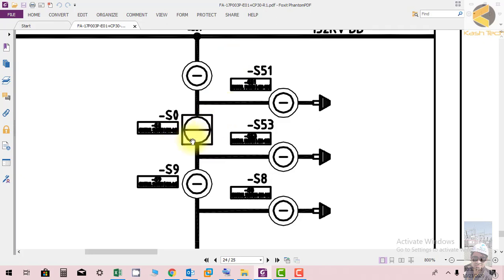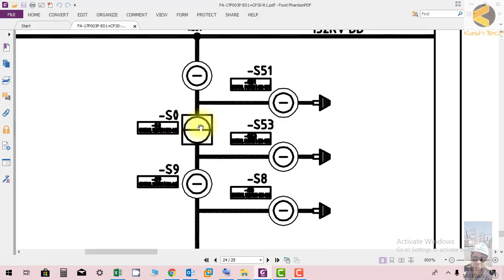As soon as the breaker in the yard is in closed position but the switch is in open position, there will be a flickering light. For example, if an operator closes the breaker and it trips due to protection, the operator can see the breaker switch is now flickering. Whenever there is a difference between the status of the control discrepancy switch and the actual status of the equipment like breaker or isolator, flickering starts. When both statuses match, flickering stops.